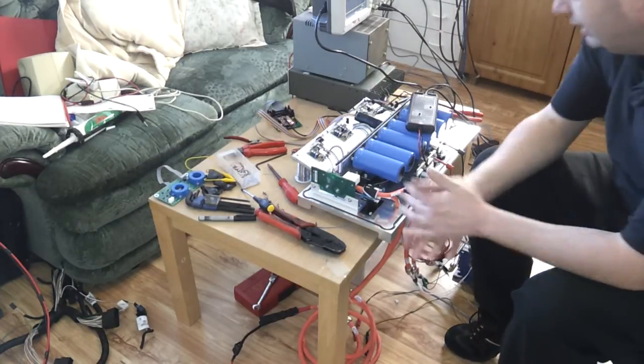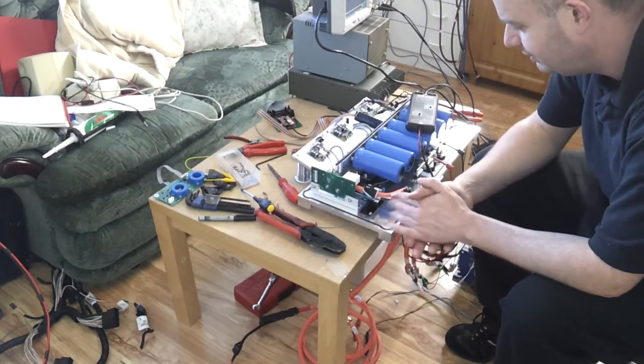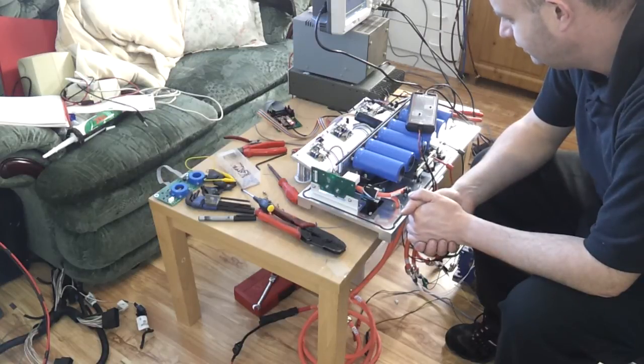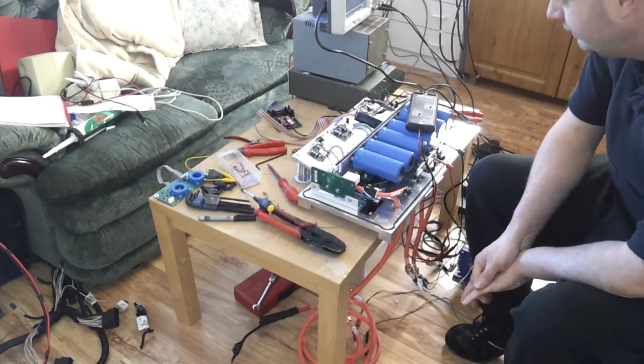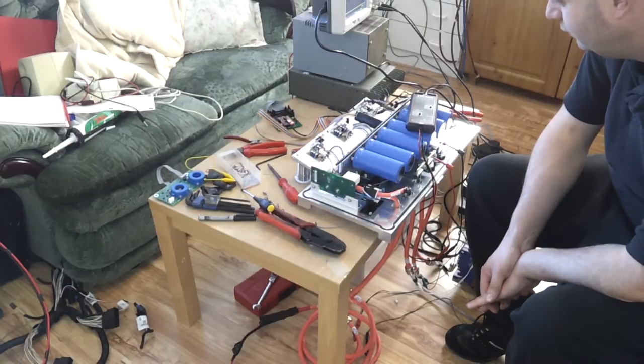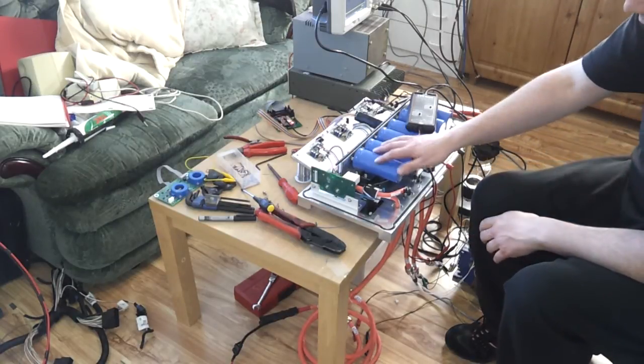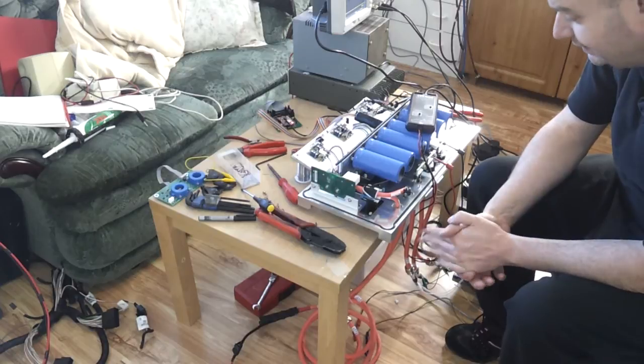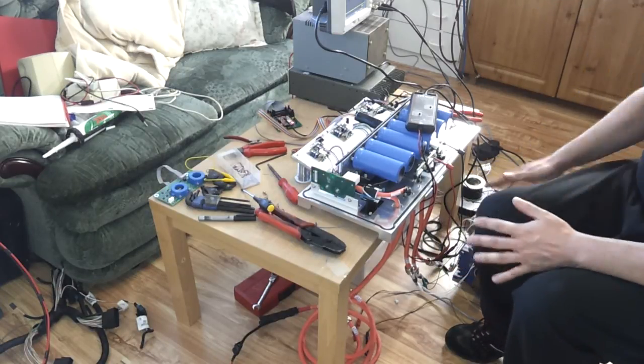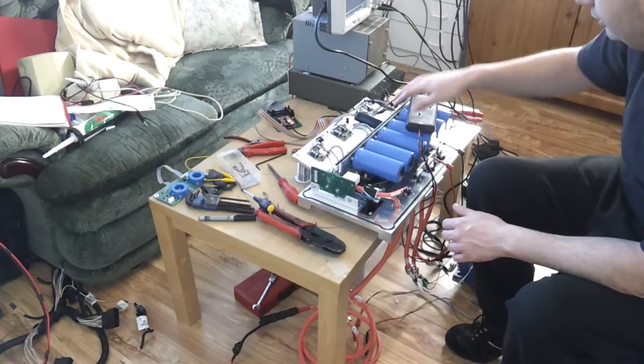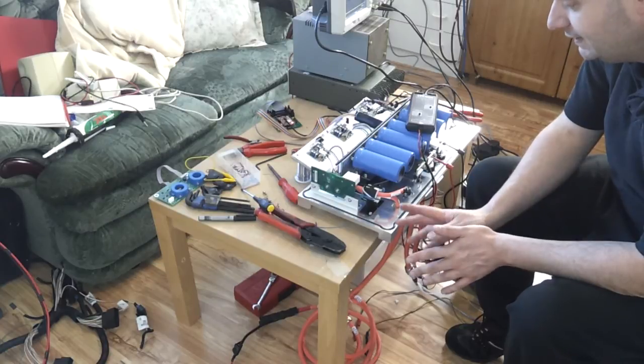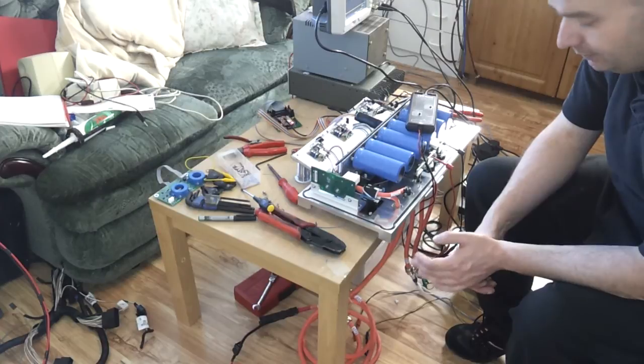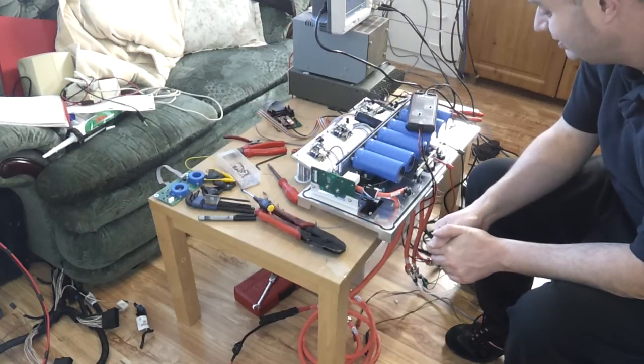The procedure to test this inverter, or indeed any inverter, pretty much first of all involves looking at all six of your gate drive signals to make sure that they're actually firing and that they're at the correct voltage levels. Once that has been done, what you want to do then is to put a low voltage DC on the bus, say 12 volts, from a power supply with a low current limit set, say 1 amp. Leaving your motor phases disconnected, put a plain 50% duty cycle on all three of the transistors. The reason you would do that is you want to look at your DC bus current and make sure that it's absolutely zero, because if there's any current being drawn, it means you're getting shoot-through on the transistors, which is bad. That will kill it in a very short space of time.